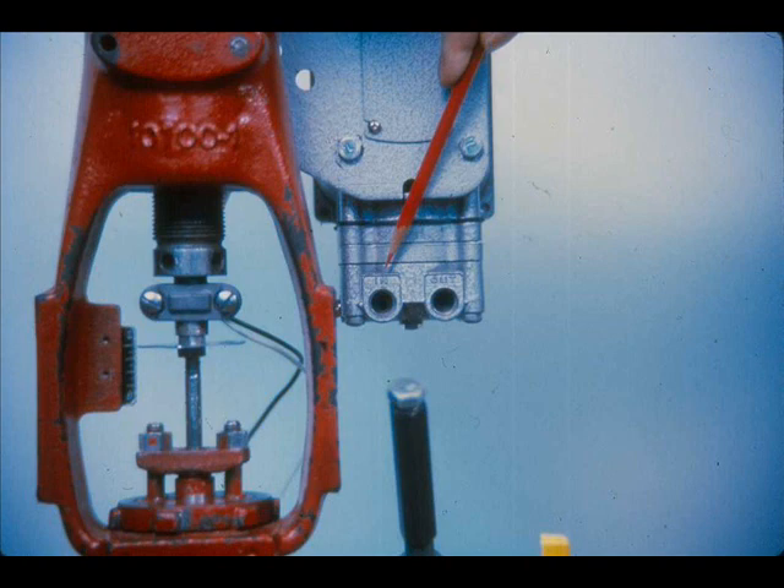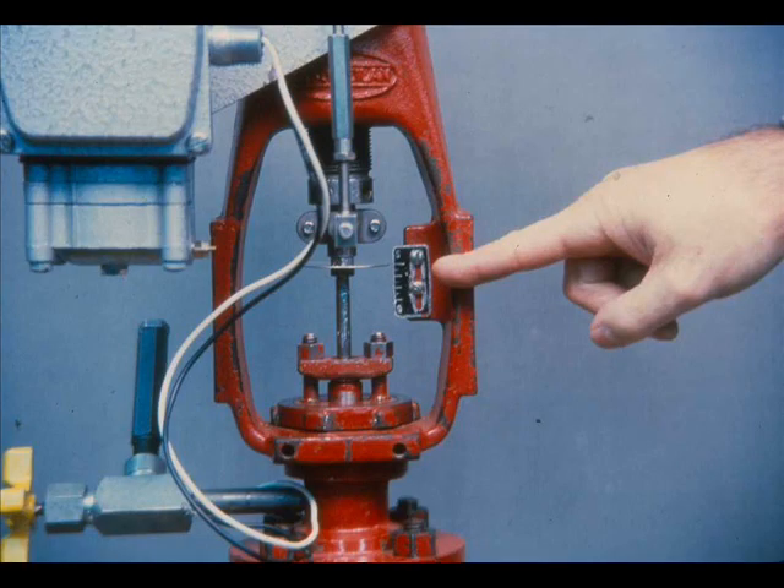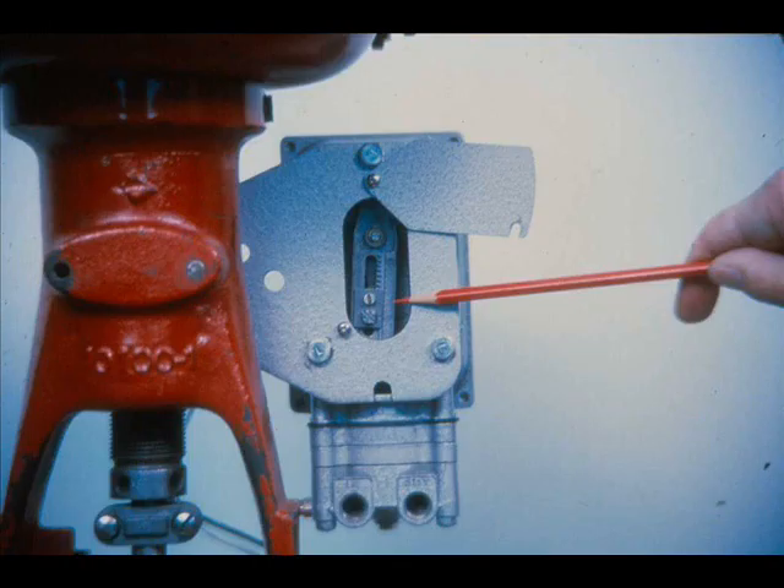Connect a regulated air supply to the quarter-inch connection on the relay marked IN. Connect the valve actuator to the quarter-inch connection on the relay marked out. To calibrate the positioner, the valve travel must be known. Loosen the index lock screw and rotate the pinion until the stroke index is opposite the marking on the stroke scale corresponding to the rated stroke of the valve.